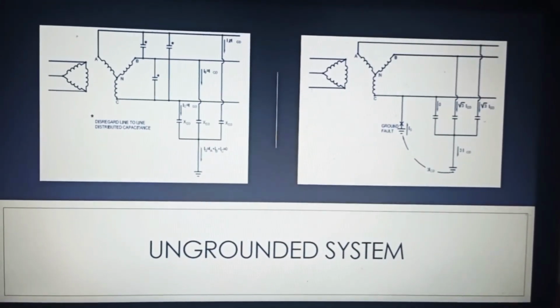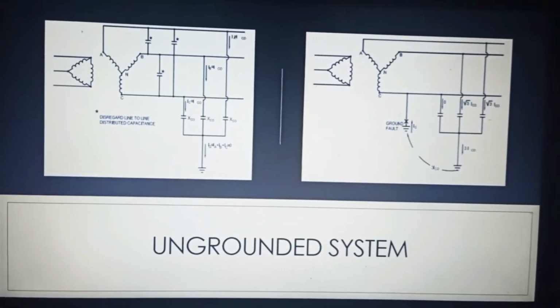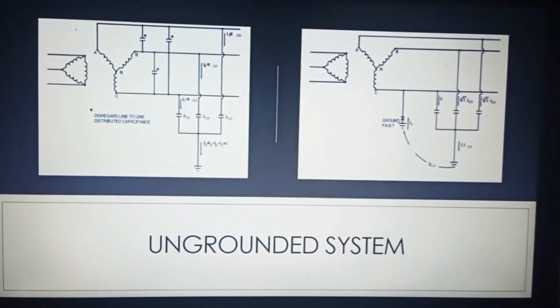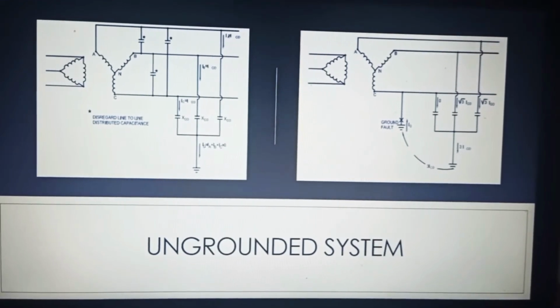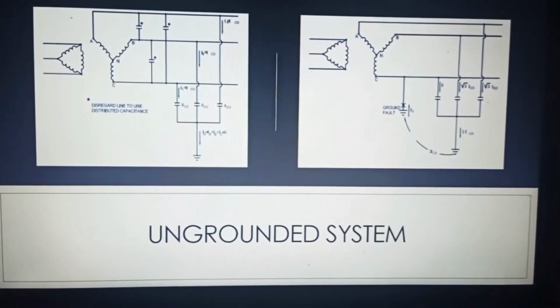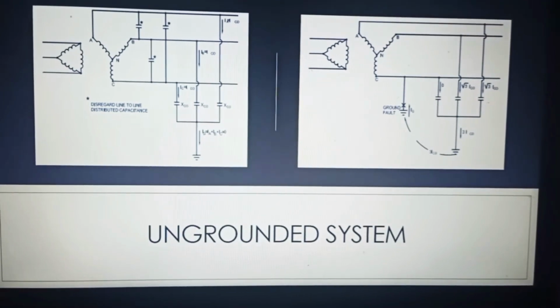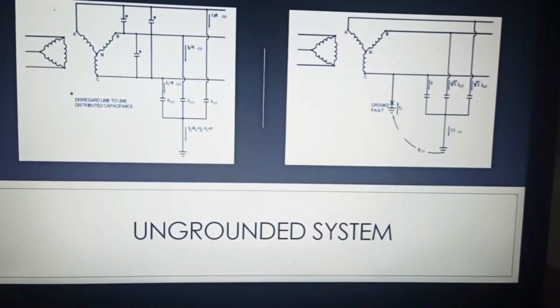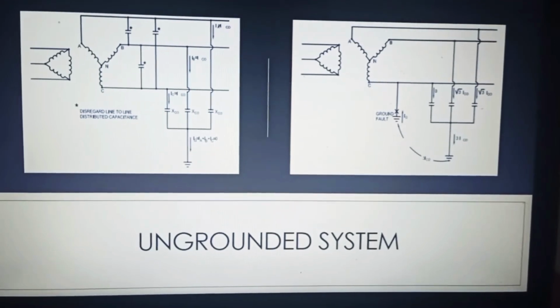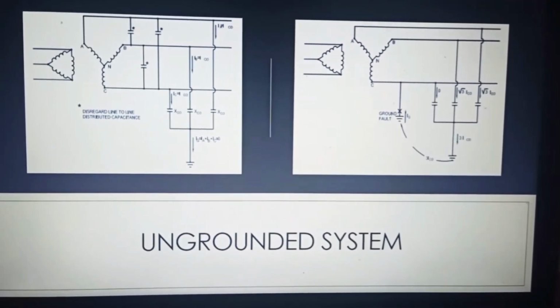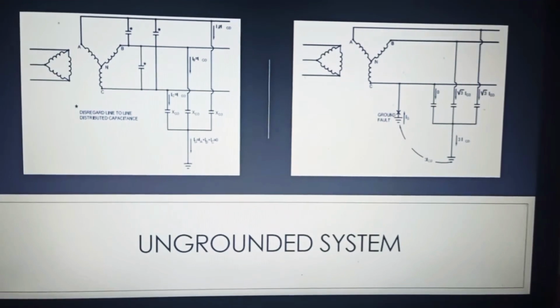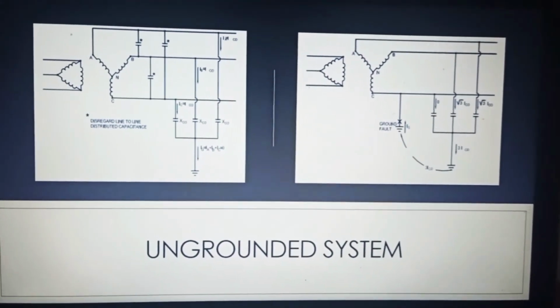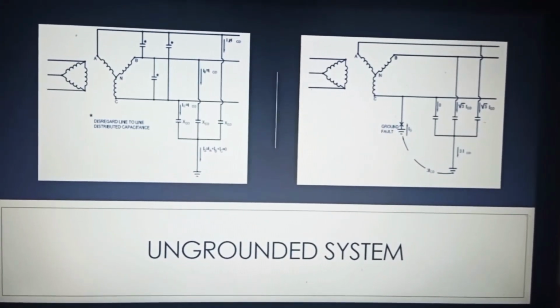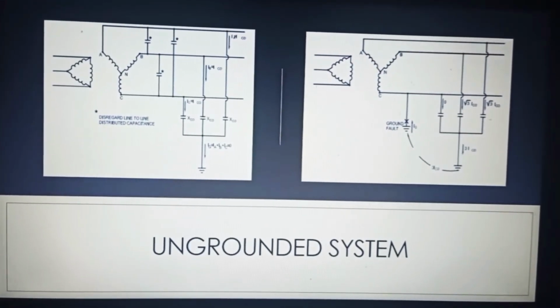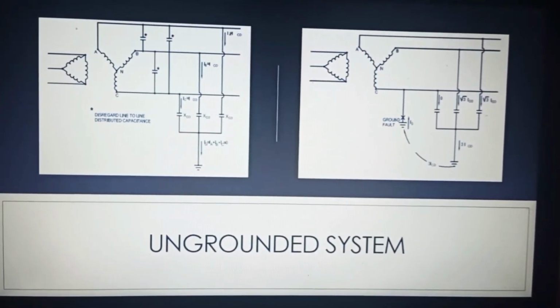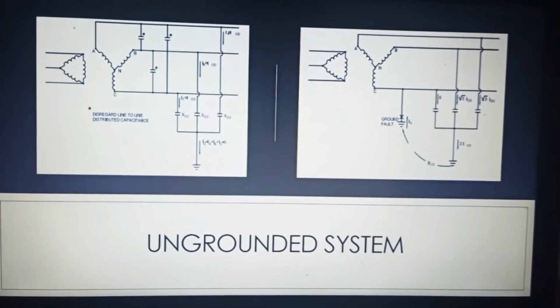In an unfaulted condition, with balanced three-phase voltage applied to the lines, the capacitive charging currents in each phase will be equal and displaced 120 degrees from one another. The phase voltages to ground will also be equal and displaced 120 degrees from one another. The vector relations are shown in part 1, picture 1. Since the neutral of the distributed capacitance is at earth potential, it follows the neutral of the transformer is also at earth potential, being held there by the capacitance to ground.